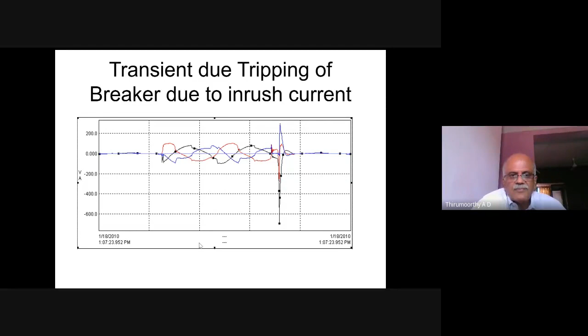So this is a graph which shows the inrush current. Whenever a transformer or heavy motors are energized, you will see that inrush current is there for a few cycles. A large amount of current is drawn by the transformer when it is charged. Consequently, that also impacts the voltage. You can see that whenever a transformer or equipment is charged, there is a voltage sag experienced by the nearby customers and nearby loads also.